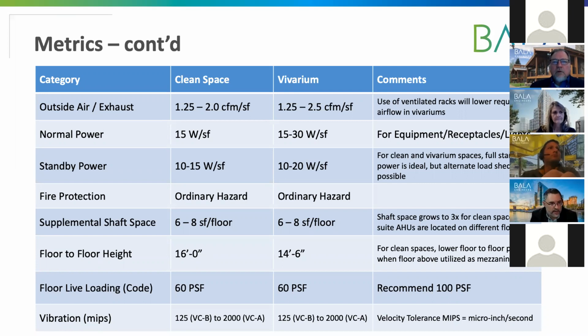And moving over to Vivarium again, with the normal power, we see a range. I'm showing a range here of about 15 to 30 watts per square foot. So typically the Vivariums are going to be very similar to labs. The reason we're showing the 30 watt per square foot is that with Vivarium, you need clean cage equipment, and they utilize steam. So if you don't have steam available or natural gas, then you're going to need to generate your steam with power. So in those scenarios, you're going to find yourself close to that 30 watt per square foot range. So it's really going to be predicated on the type of equipment you have in your cage wash area, whether you have the 15 or the much higher value at 30.